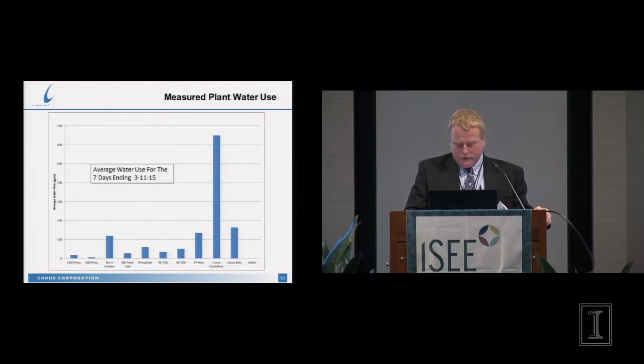Some of them are process, some of them are cooling water related. And like I said, if you don't measure it, it's invisible to people and you'll never be able to manage it. This was really important for us. I can't tell you how many meters we have in the plant that tell us how much water we're using. We're highly automated, we use Allen Bradley PLCs. We have an HMI, the guys run the plant with the computers. All the data that we use is stored in a data historian called PI, and you'll see some slides of that later. So we can look at anything that's going on in the plant, and by having all this measured utility information, now you have the tools you need to manage it.